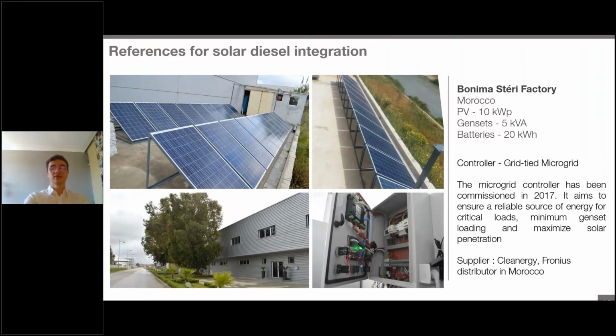We also have examples of control sites. Here, for instance, the Elum microgrid controller was installed to control the PV system, gensets, and battery on a microgrid in Morocco, where we work with Cleanergy, a Fronius distributor there. The Elum controller ensures that at all times we maximize PV penetration and control the system correctly according to actual possible PV production, the energy stored in the batteries, the minimum genset loading, and other challenges at stake in microgrids, as mentioned before.